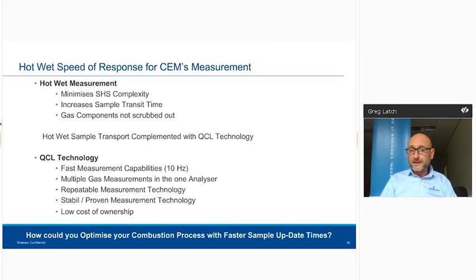It is complemented with the QCL technology and the elevated cell. QCL has fast measurement capabilities, up to 10 Hertz for example, so we're doing multiple points and components of interest, multiple gases. In this particular case it can fit up to 6 laser streams, a mix and match of TDL and QCL within the analyzer system in its own right. With up to 6 laser systems we can do up to 12 analytes. Depending on your gas composition, you may only have a number of lasers in there and measure, for example, 3 to 4 analytes in the one analyzer.